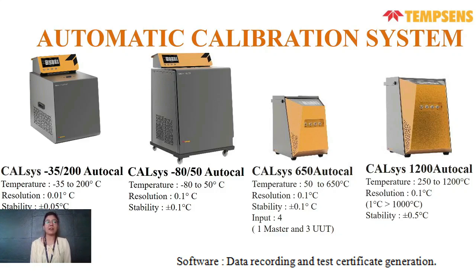A few are mentioned here. Calsys minus 35 to 200 AutoCal with temperature range minus 35 to 200 degrees centigrade, resolution 0.01 degrees centigrade, stability plus minus 0.05 degrees centigrade. Calsys minus 80 to 50 AutoCal, temperature range minus 80 to 50 degrees centigrade, resolution 0.1 degree centigrade, stability plus minus 0.1 degree centigrade. And Calsys 650 AutoCal with temperature range 50 to 650 degrees centigrade, resolution 0.1 degree centigrade, stability plus minus 0.1 degree centigrade.